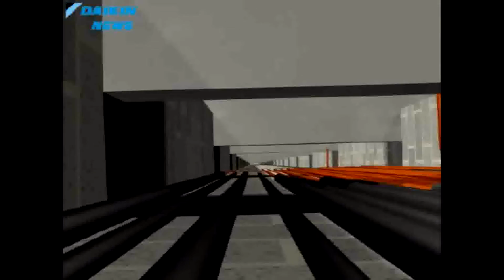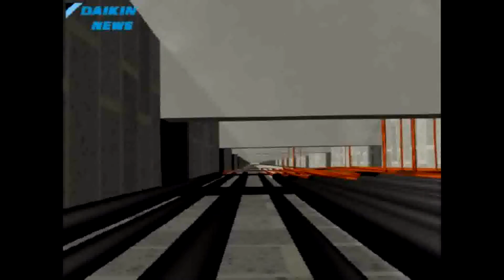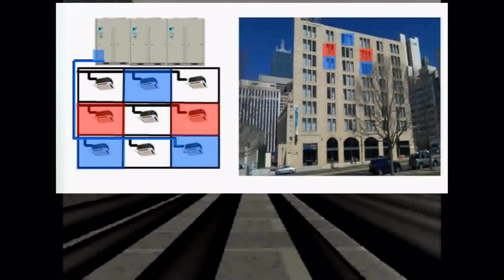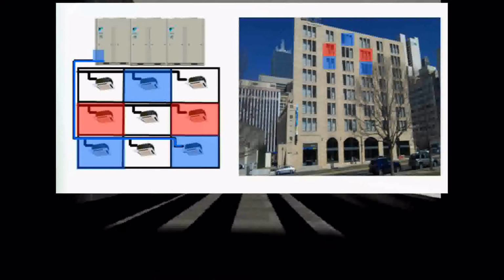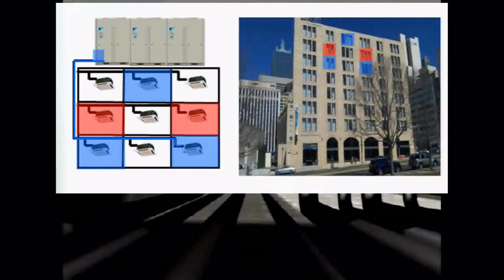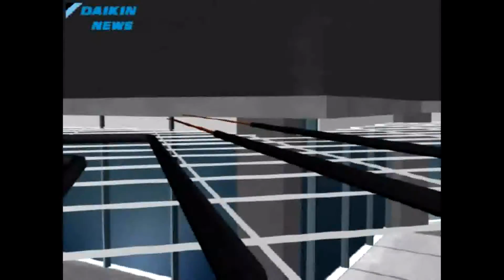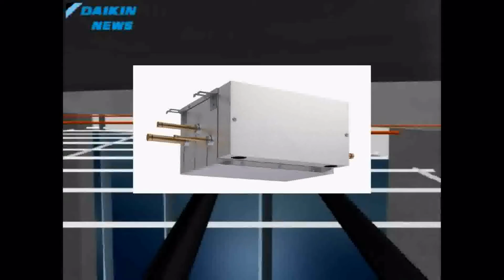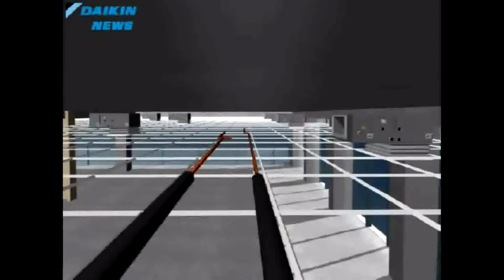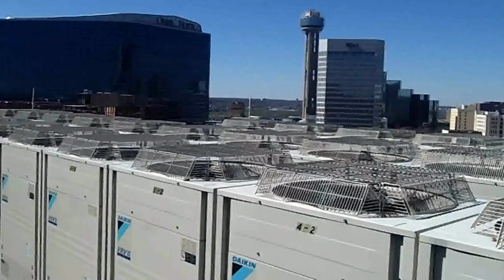The Aloft fan coils in the guest rooms are supplied by a heat recovery system. A heat recovery system allows for some rooms to be in heat, some rooms to be in cooling, or all in heat and all in cooling. This is made possible by a branch selector box. The branch selector box in this application was installed next to the fan coil units in the room.